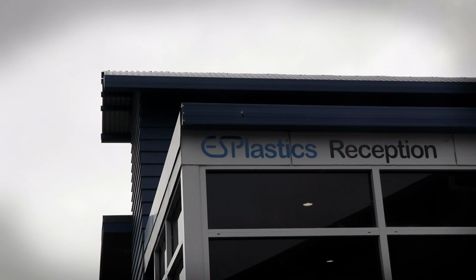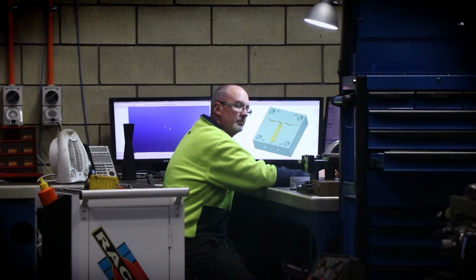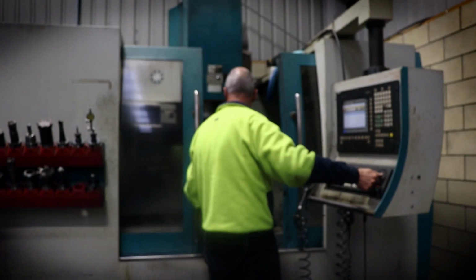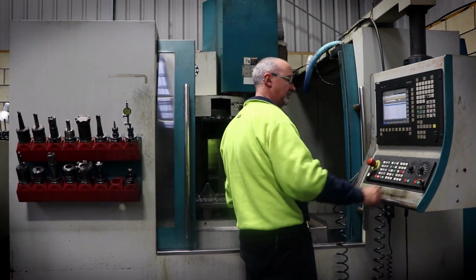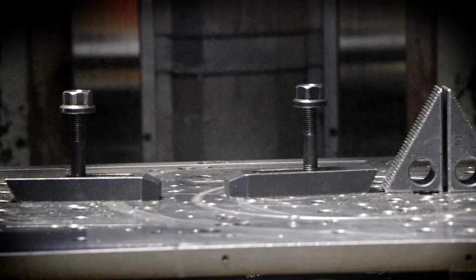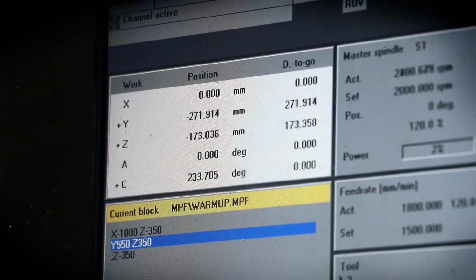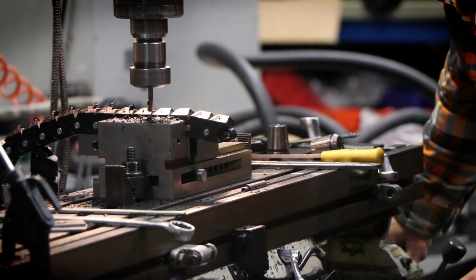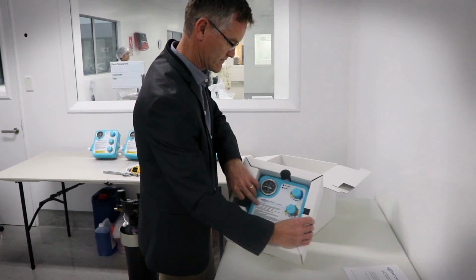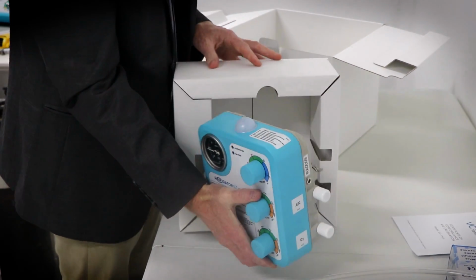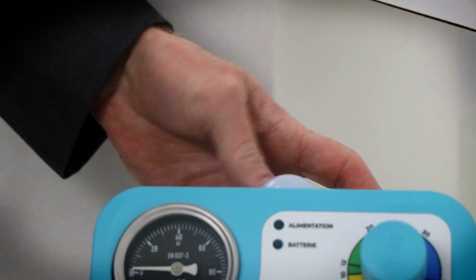Part of the New Zealand government's response to the pandemic was a COVID Innovation Fund. This supported RespiratorNZ to turn the VC pandemic ventilator into a reality. To qualify for the Innovation Fund, there were some rigorous international standards to be met. It's a volume-controlled ventilator, so there's standards that were put out by the UK around flow rates and times and pressures, what material the thing is made from, how durable it is, how long the battery life lasts. We have a full validation document to prove all of the parts of the standard are met.